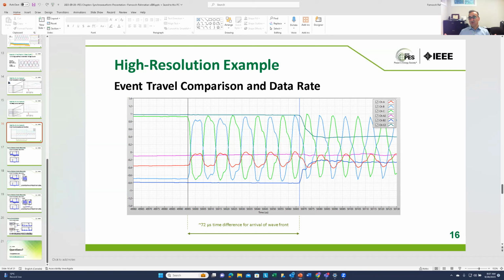So that's about 250 milliseconds, a quarter of a second. Megahertz data, 3-phase, you have that high resolution. At the same time, it samples at 14.4 kilohertz, like the standard power quality rate, 1 second before and 15 seconds after. So a lower sampling rate, but a wider window. And it also samples PMU data 4 minutes before and 10 minutes after for every event.